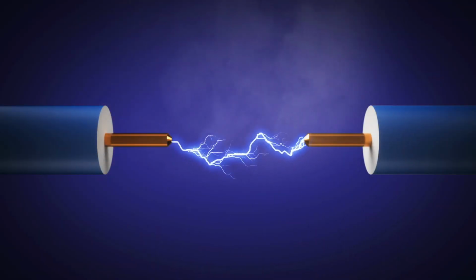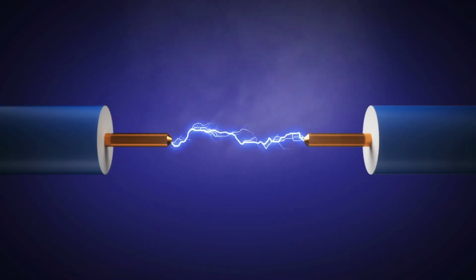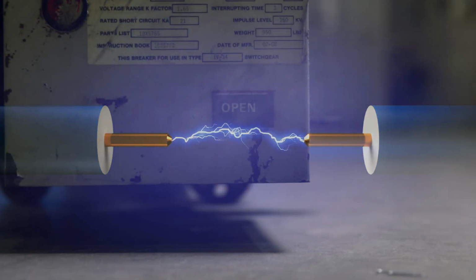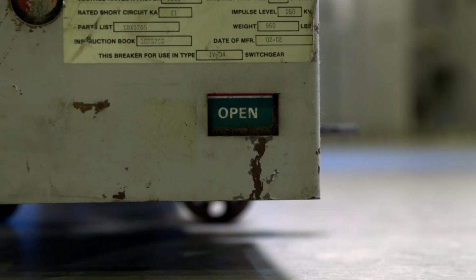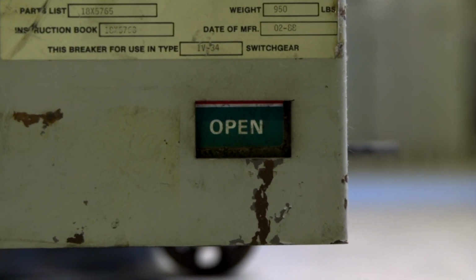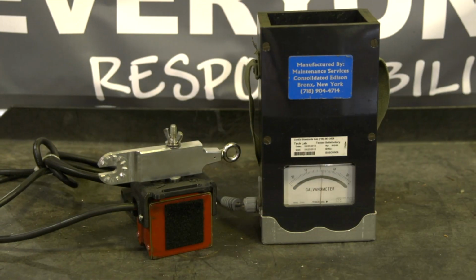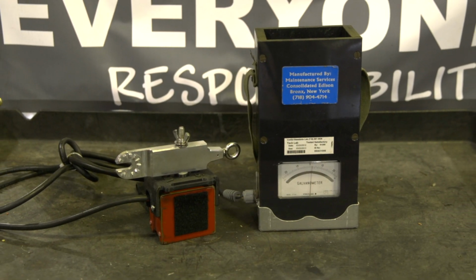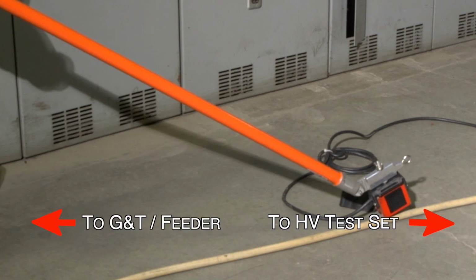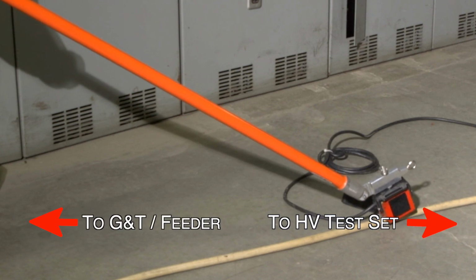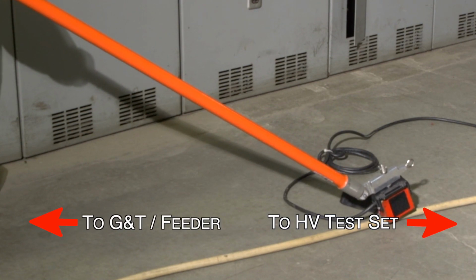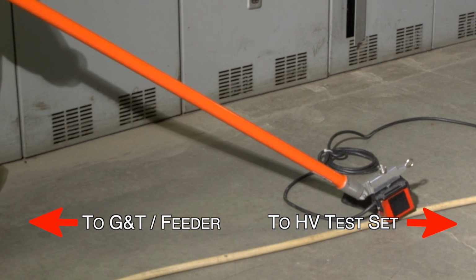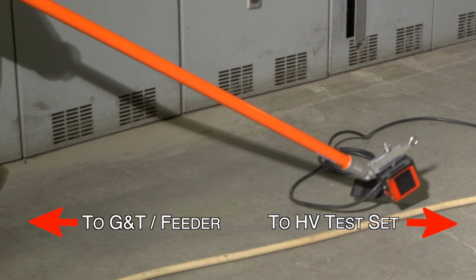At this time you have successfully applied high voltage on the feeder. As per your operating order, you verified the correct value and duration given to you by the district operator. You also verified the ground and test device is open, and high voltage is now traveling out on the correct feeder. Now let's check the high voltage using the galvanometer. The first step is to position yourself opposite of the test set cables. Remember, when the G and T is open, the high voltage cables become an extension of the feeder. Be sure to maintain a safe distance utilizing your live line tools and appropriate minimum approach distances, while testing each phase, one at a time.